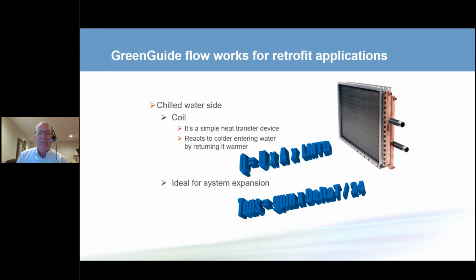Many people think that a coil is designed for a particular temperature difference and flow rate. It's not. It's selected there. I tell people coils are just dumb pieces of metal. They don't know anything. They don't know how to do anything. Their purpose is to transfer heat. When we give a coil colder water, it will use less of that water, and we will get the same heat transfer. Because a coil's heat transfer is the U value times the area times the log mean temperature difference. And the cooling capacity is the flow rate times the temperature difference.